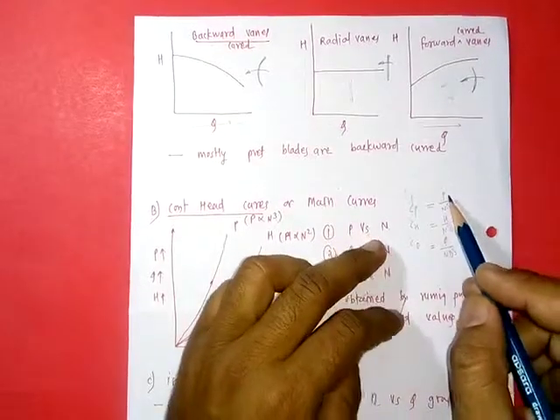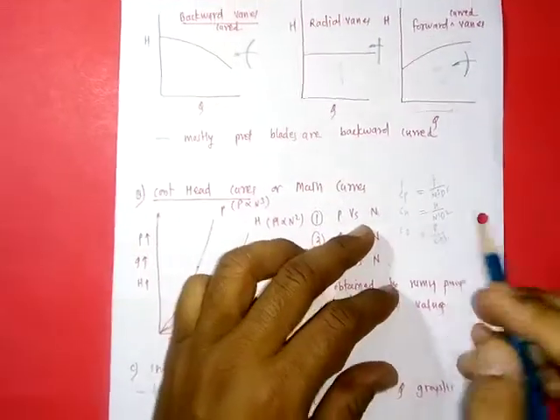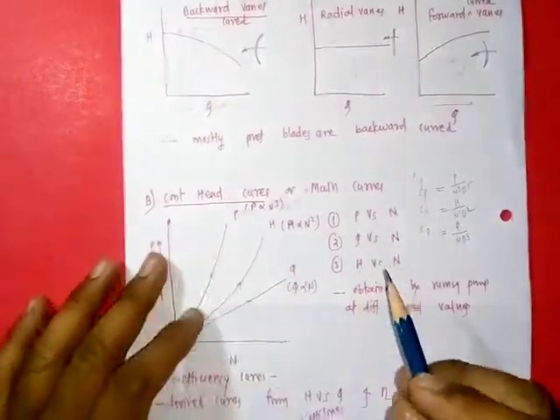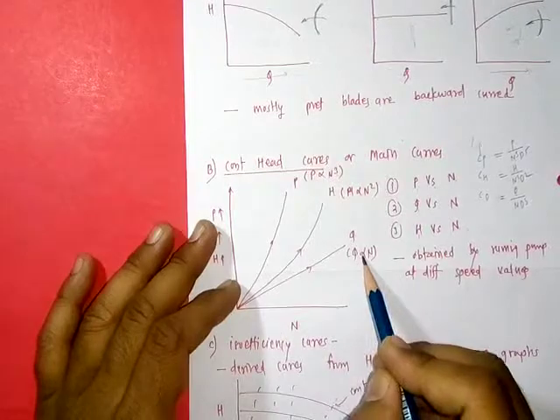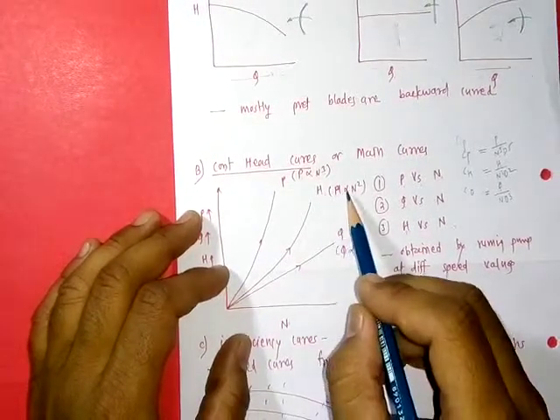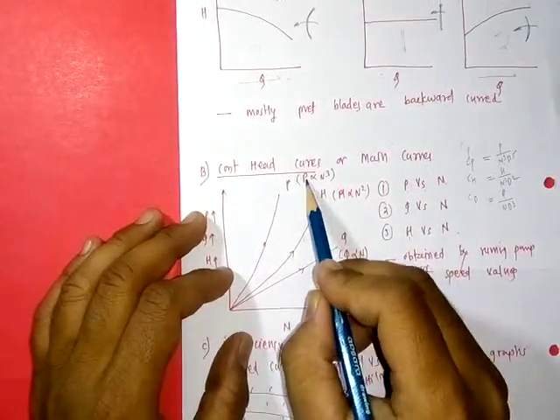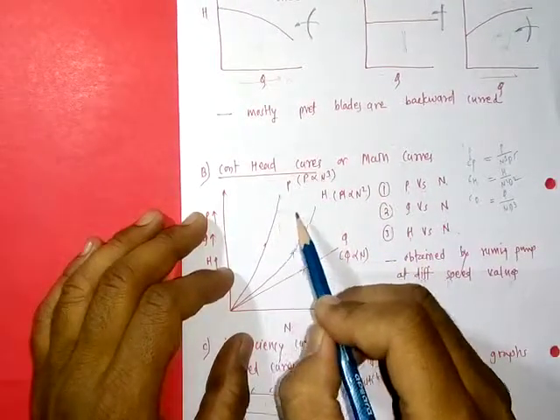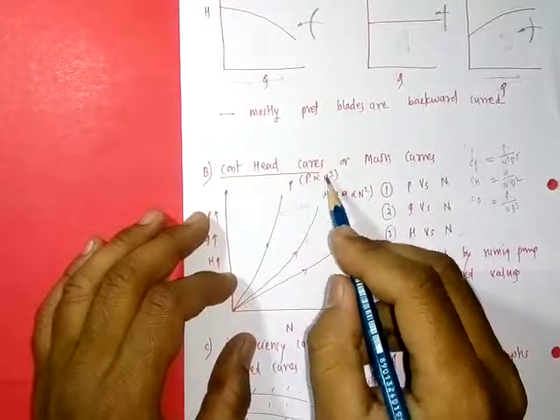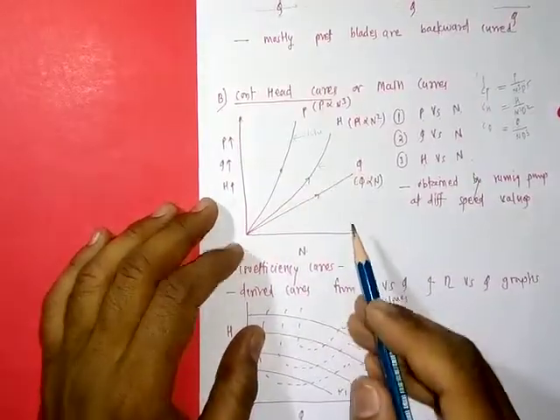From these coefficients, power P is proportional to N³, head H is proportional to N², and discharge Q is proportional to N. So variations of Q are linear with N, variations of H are parabolic with N, and variations of power versus speed are cubic because P is proportional to N³. These are the constant head curves or main curves.